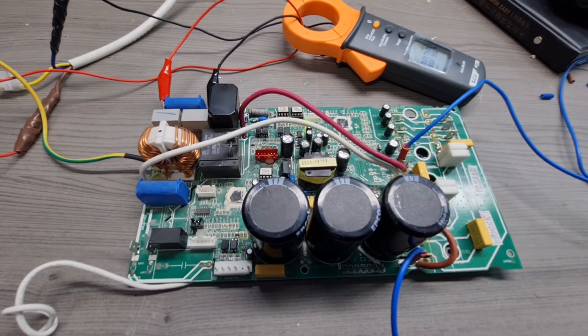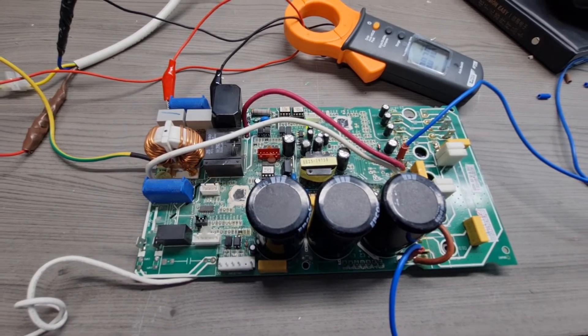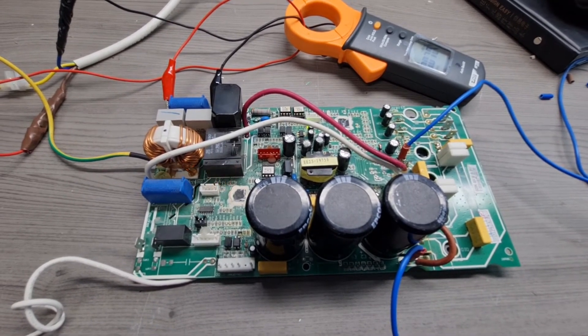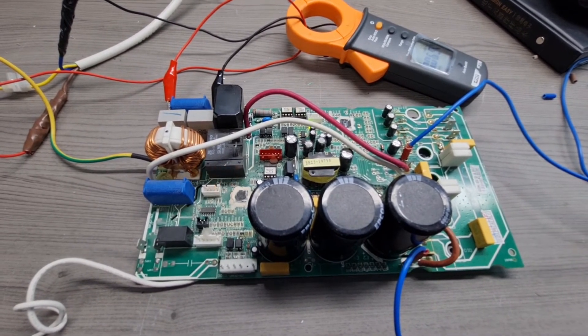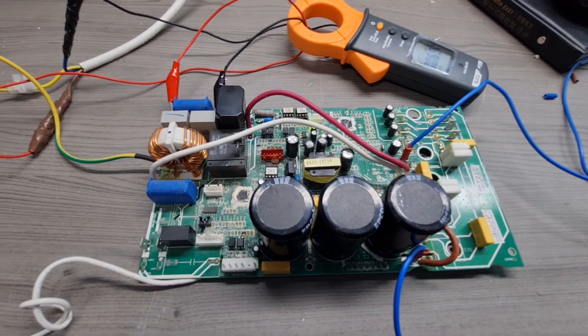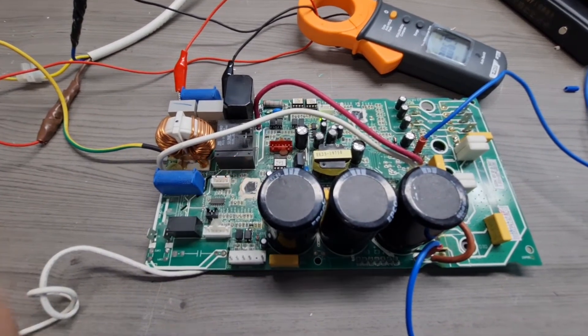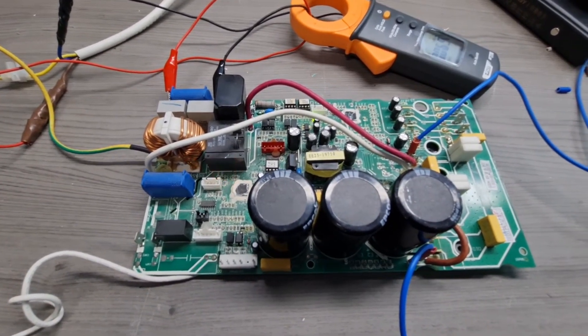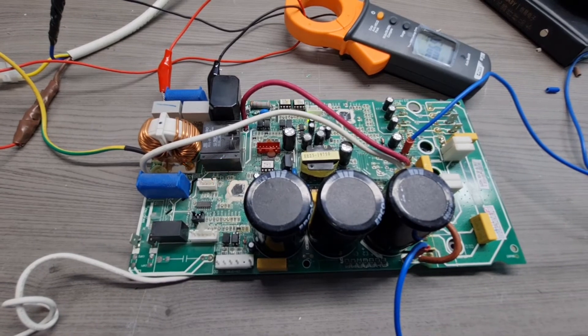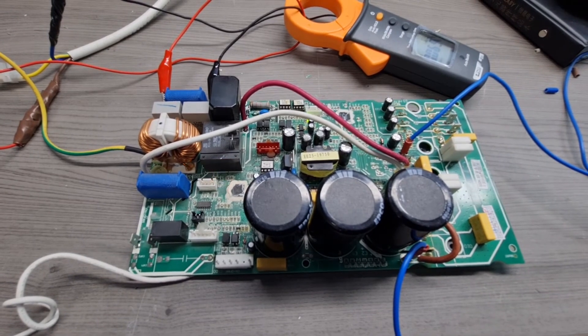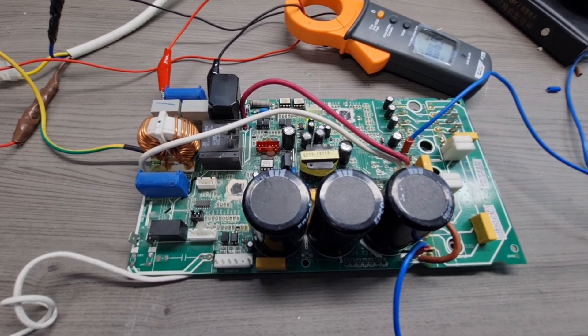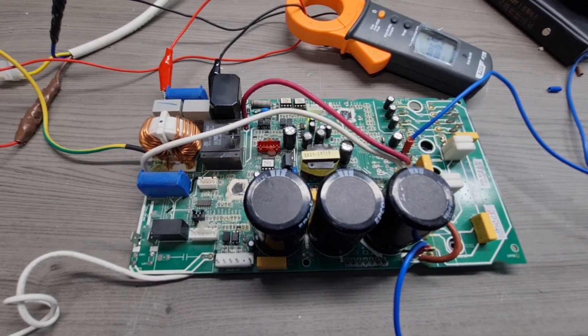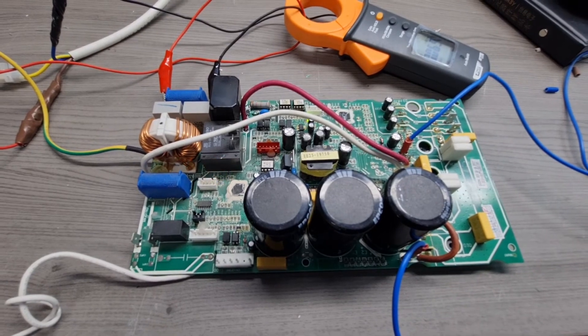So one must be very careful because typically the RCD, we would have one RCD with 30 milliamps of current, and today with these switch mode power supplies and with inverter driven compressors, that 30 milliamp for an entire house or an entire apartment might not be sufficient.